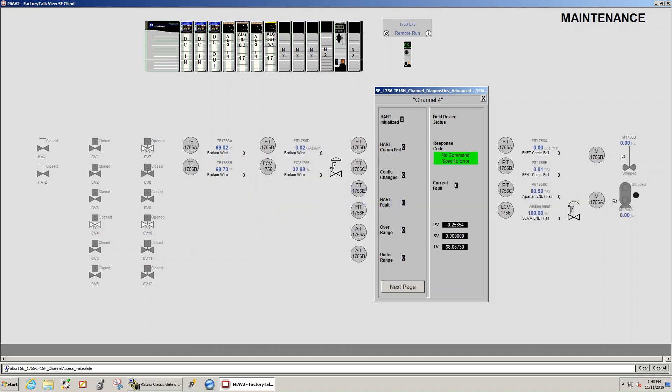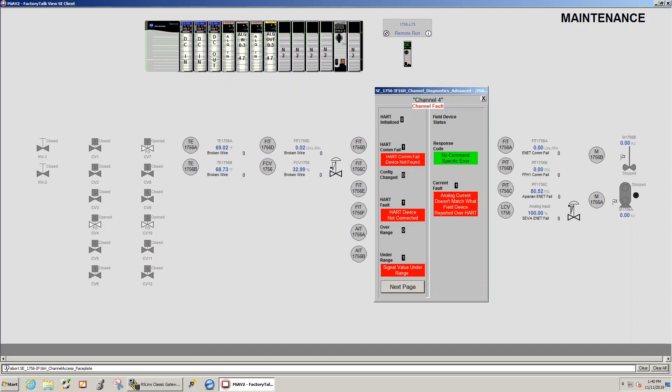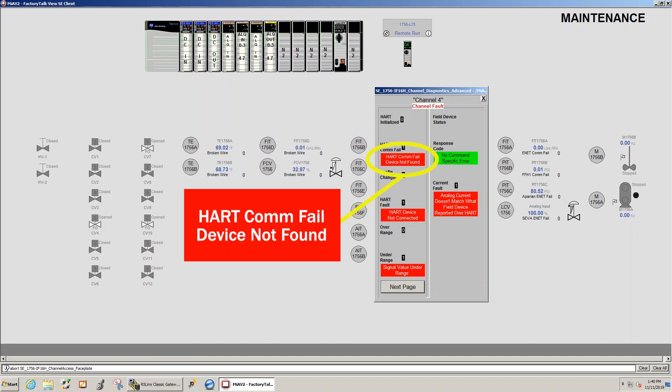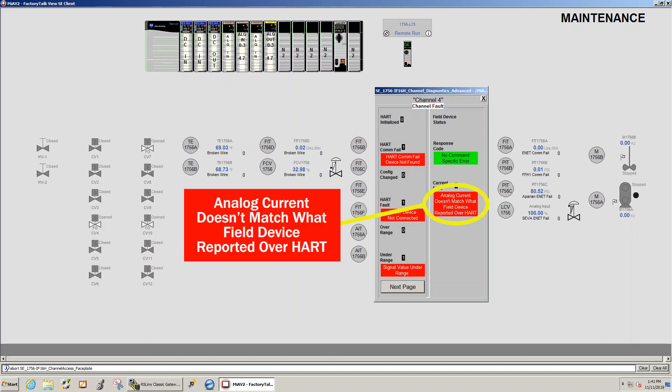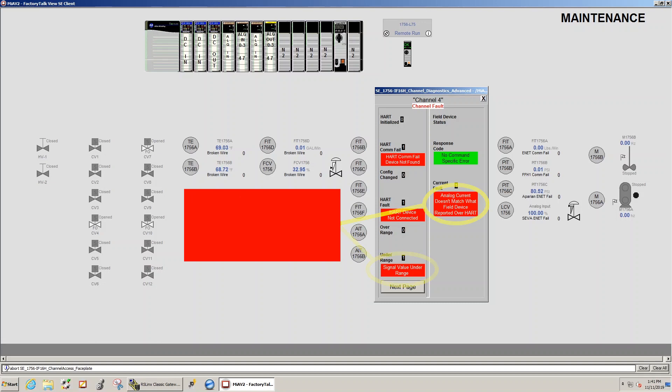Now I am going to cause an error on one of our field devices so we can see the diagnostics in action and troubleshoot the field device without ever directly interacting with it. After causing the error I get a HART com fail with the status message HART com fail device not found, a HART fault with the status message HART device not connected, a current fault with the status message analog current does not match with the field device reported over HART, and finally an under range fault with the status message signal value under range.